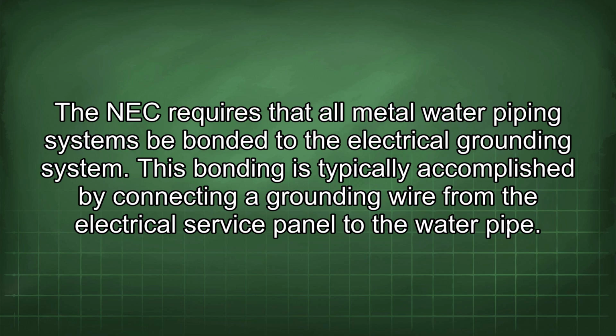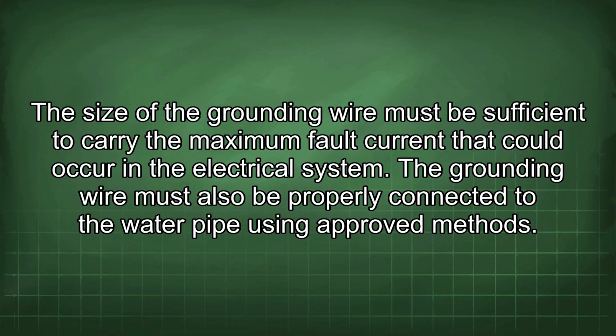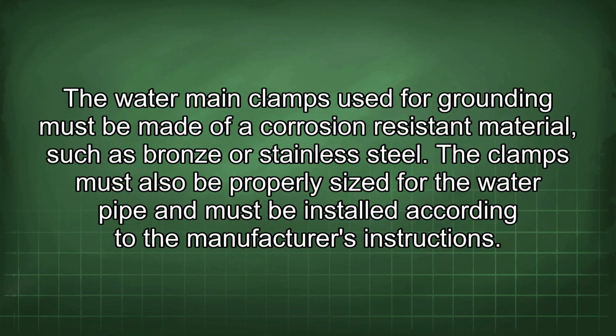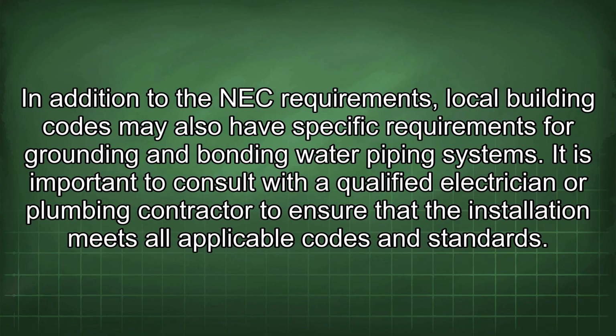The NEC requires that all metal-water piping systems be bonded to the electrical grounding system. This bonding is typically accomplished by connecting a grounding wire from the electrical service panel to the water pipe. The grounding wire must be sized to carry the maximum fault current that could occur in the electrical system, and must be properly connected using approved methods. The water main clamps used for grounding must be made of a corrosion-resistant material, such as bronze or stainless steel, properly sized for the pipe, and installed according to the manufacturer's instructions. Local building codes may also have specific requirements, so it is important to consult with a qualified electrician or plumbing contractor to ensure that the installation meets all applicable codes and standards.